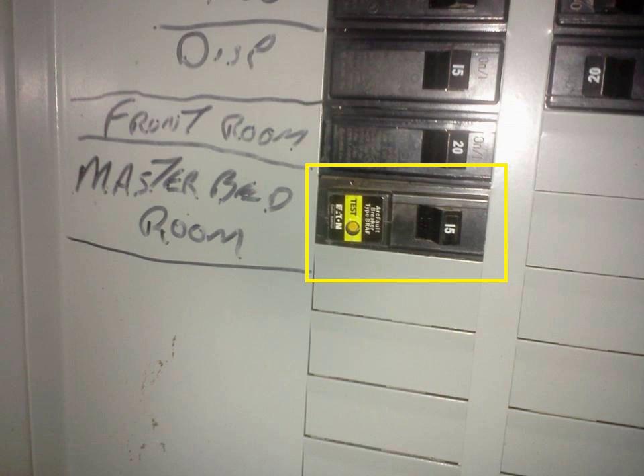Heat comes from power dissipation. This energy, when dissipated in a small junction area, can generate temperatures above 1000 degrees Celsius and can ignite most flammable materials. Bad wiring junctions can occur in utilization equipment, cords, or in situ wiring and especially in a defective switch, socket, plug, wiring connection, and even at the circuit breaker or fuse panels.